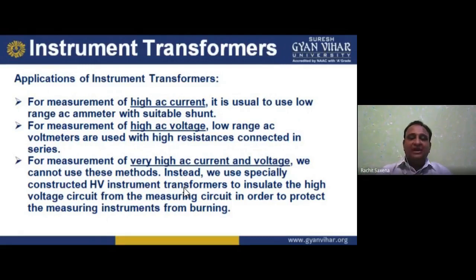For measurement of high AC voltage, low range AC voltmeters are used with a high resistance connected in series. In a voltmeter we connect resistance in series, in an ammeter we connect resistance in parallel. For measurement of very high AC current and voltage, we cannot use this method. Instead, we use specially constructed high voltage instrument transformers to insulate the high voltage circuit from the measuring circuit.